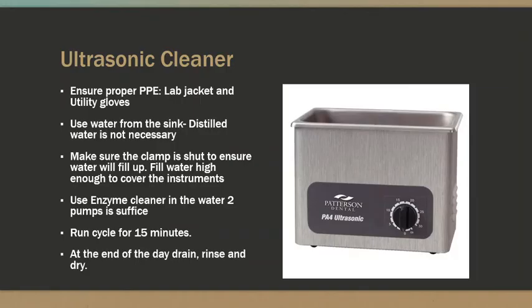An alternative to the Miele is an ultrasonic cleaner. We do have two in the clinic, a larger one and a smaller one. Of course, you're going to use your proper PPE, and you will just fill this with water from the sink. Distilled water is not necessary for this. You want to make sure that the clamp is shut to ensure that the water will fill up when you're filling it up. And you're going to fill the water high enough to cover the instruments that you're putting into the ultrasonic. You'll use enzyme cleaner in the water. 2 pumps is suffice, and you'll run the cycle for 15 minutes.